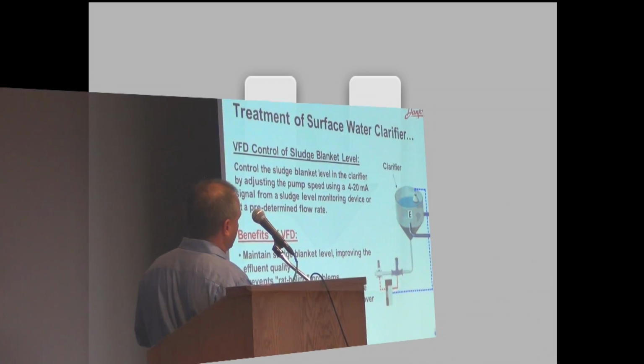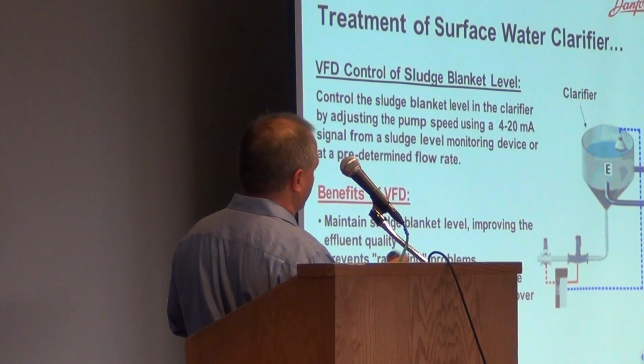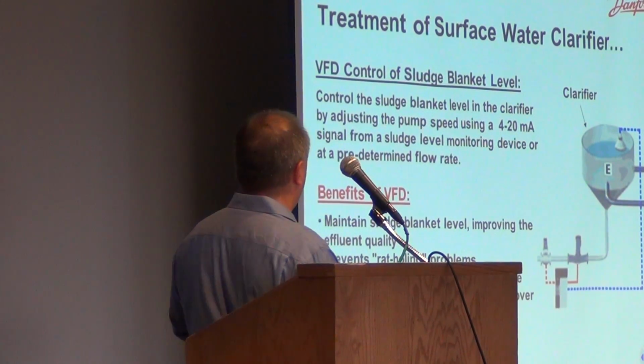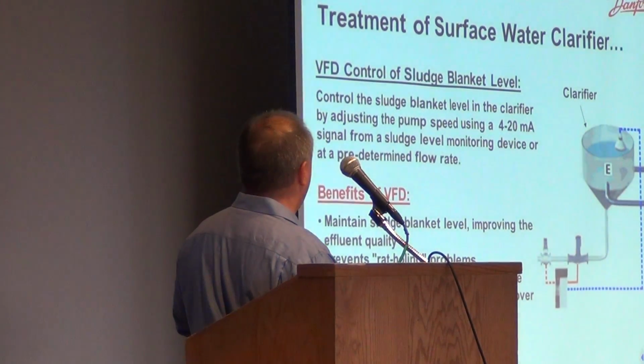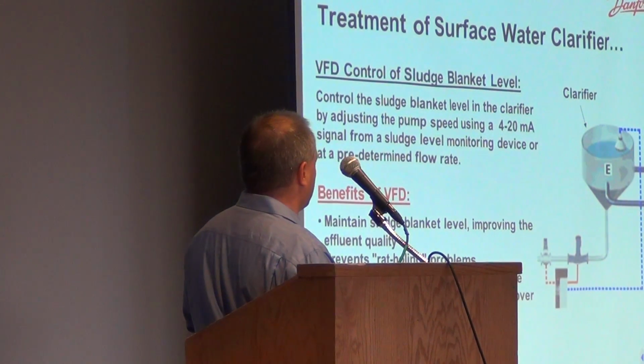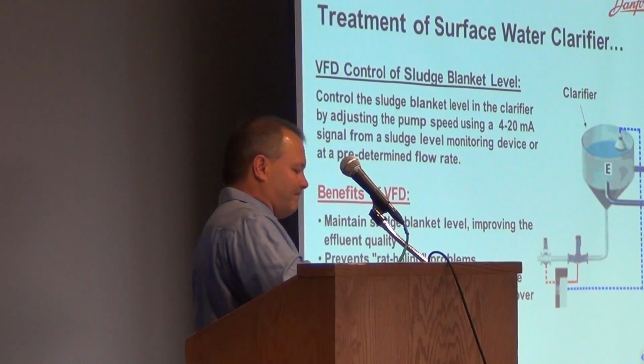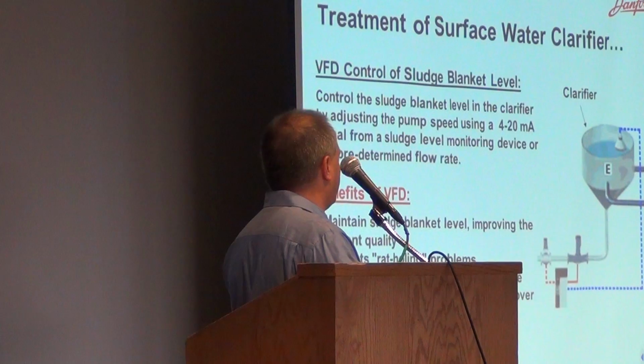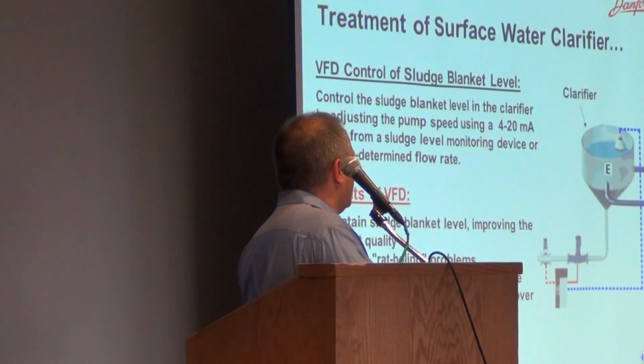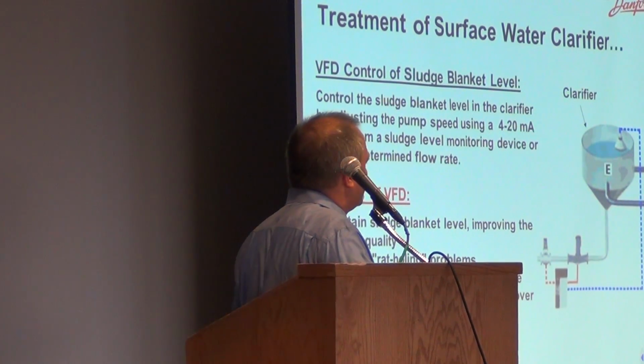Once again, this is the rat holing problem. The drive helps by maintaining the flow constancy. The sludge is a constant flow out. We don't get that little suck of water, the rat hole as they call it. It enhances the pump. It also maintains the pump at a constant speed so you get a better constant flow of material through the system.